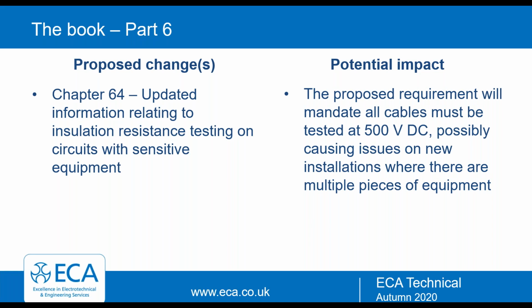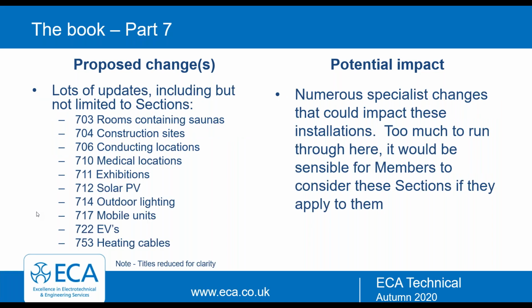Omar, if you wouldn't mind just skipping on to the next slide. Questions come in: isn't it the case that unwanted tripping is caused by protecting 6 circuits on one RCD? Well, it could be, it depends. There's already a regulation that talks about limiting the amount of earth leakage per RCD, so that's already taken care of in the existing regs.